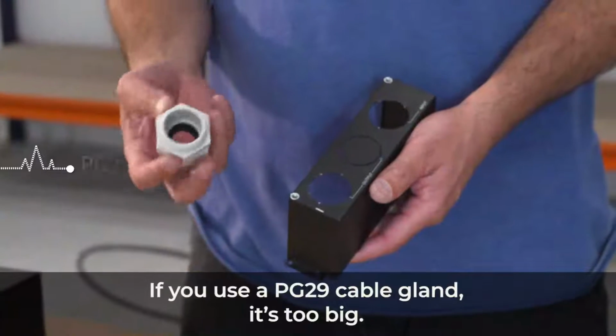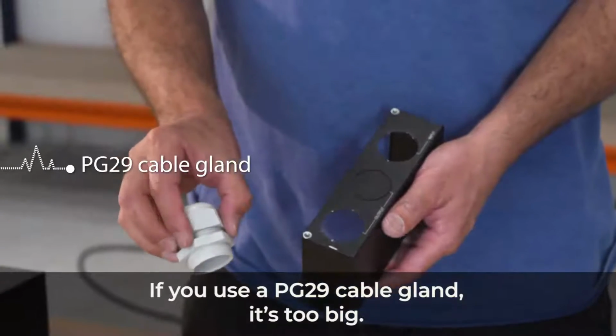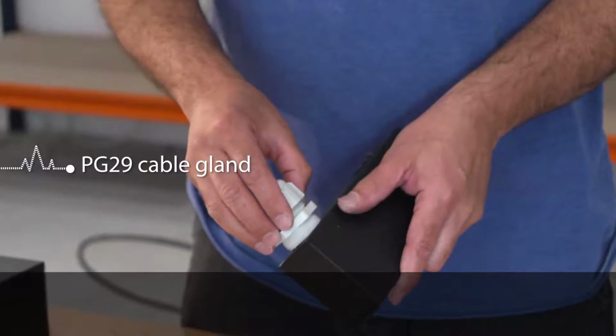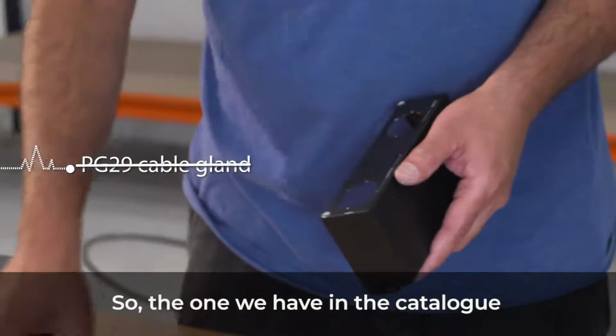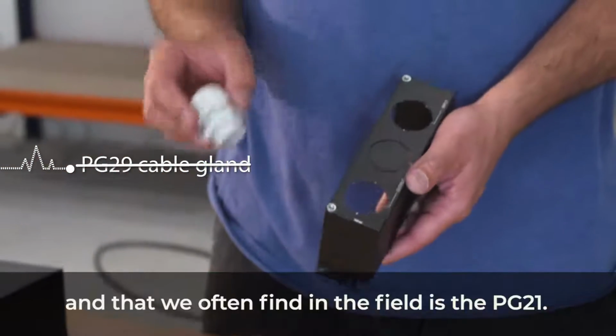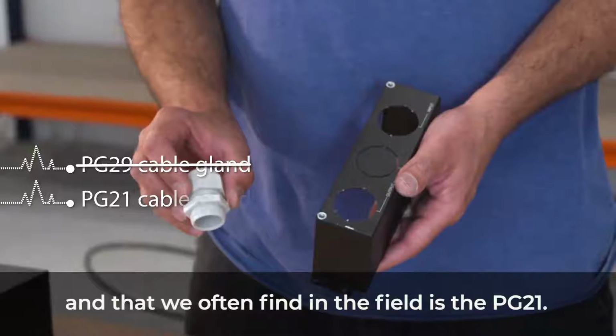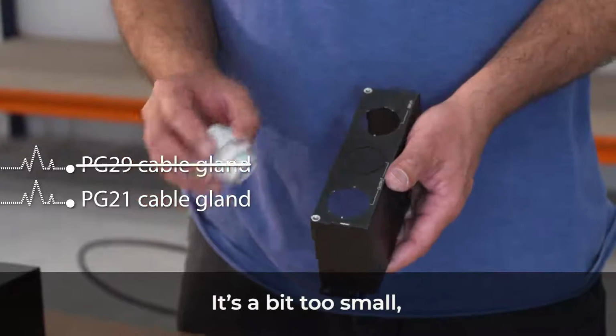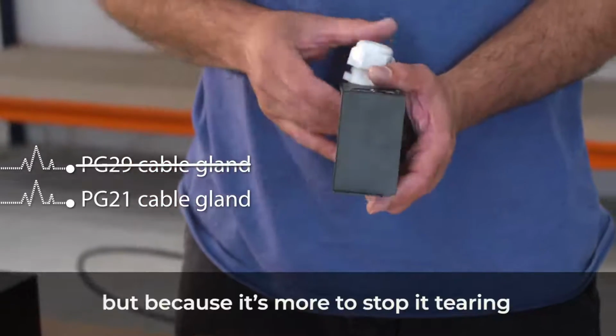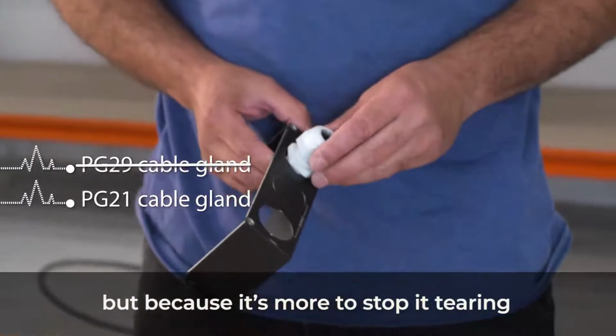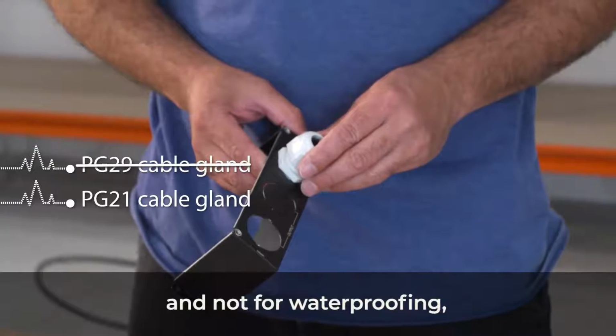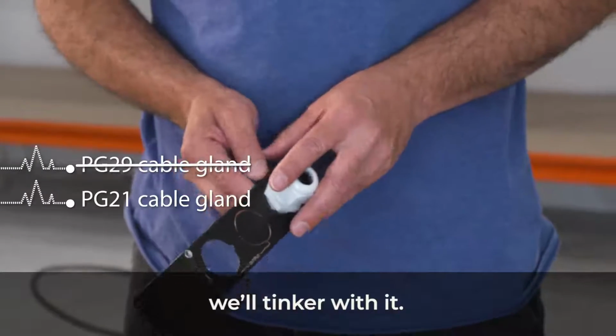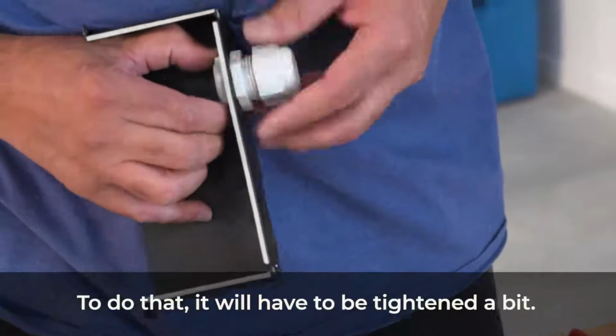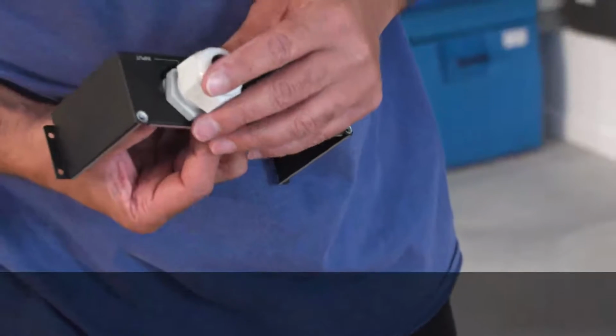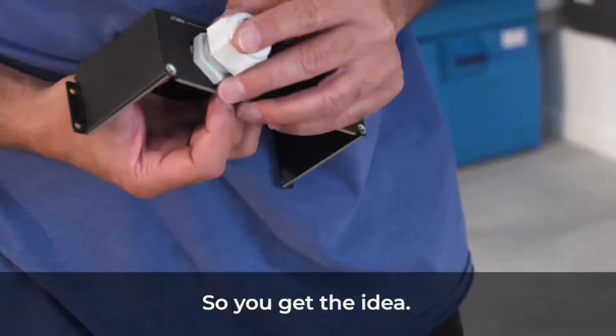If you use a PG29 cable gland, it's too big. So the one we have in the catalogue and that we often find in the field is the PG21. It's a bit too small, but because it's more to stop it tearing and not for waterproofing, we'll tinker with it. To do that, it will have to be tightened a bit. So you get the idea.